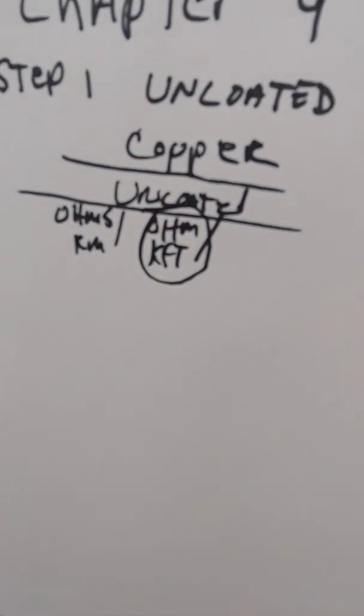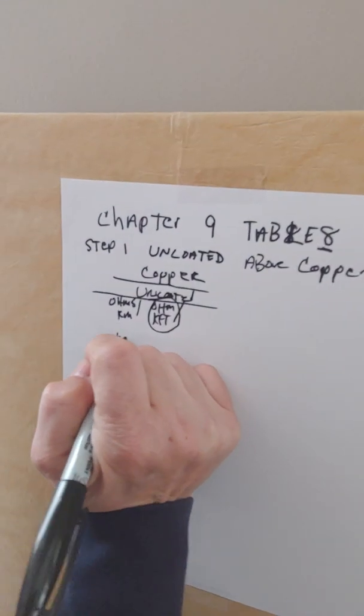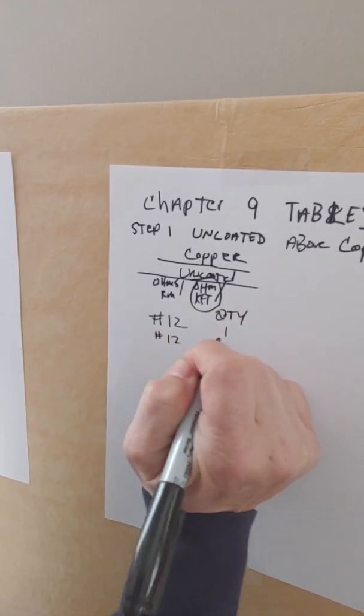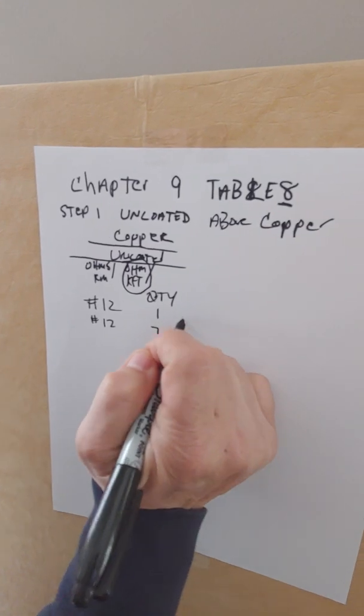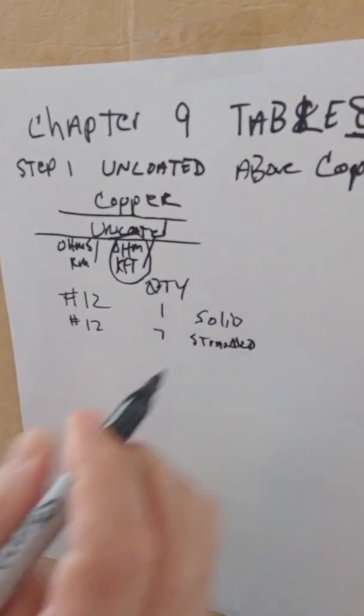We go to a number 12, and if everybody looks right here you're going to see my finger at number 12 wire. You see the AWG right there. We go to 12 and you see the quantity, one and seven. The number 12 with quantity one means solid, and the number 12 with seven means stranded.